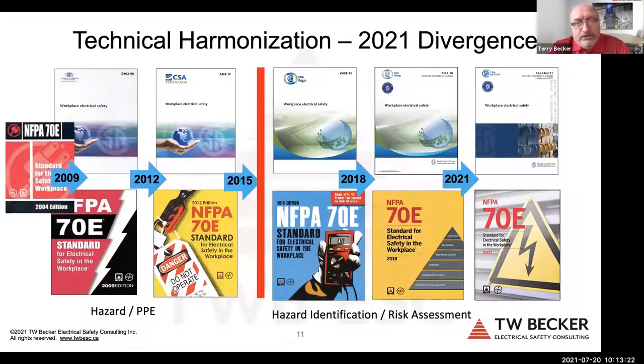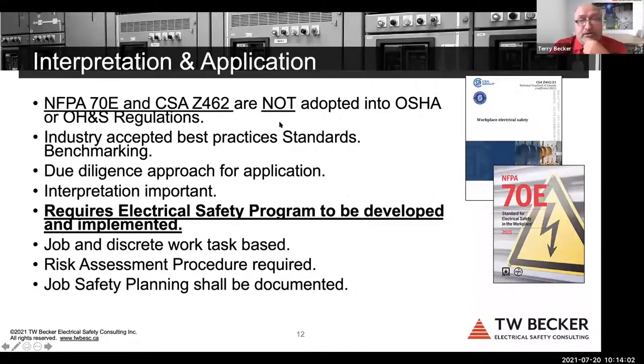So just a quick montage of the 5 changes, or the 5 additions, of Z462 to 70E. Initially, 70E and Z462 were hazard PPE based, and now they're hazard identification and risk assessment based, and that continues to evolve in the latest edition. There's a lack of understanding of the risk assessment procedure, and I think a lot of companies that have electrical safety programs do not have an electrical hazard risk assessment matrix, do not do work task based qualitative risk assessments, and again, that's another gap. But the standards are job, and then discrete work task based and risk assessment based. So interpretation and application: these standards are not adopted into H&S regulations in Canada or the US. They're industry accepted best practices. They allow an employer that has workers exposed to arc flash and shock hazards to demonstrate significant due diligence.